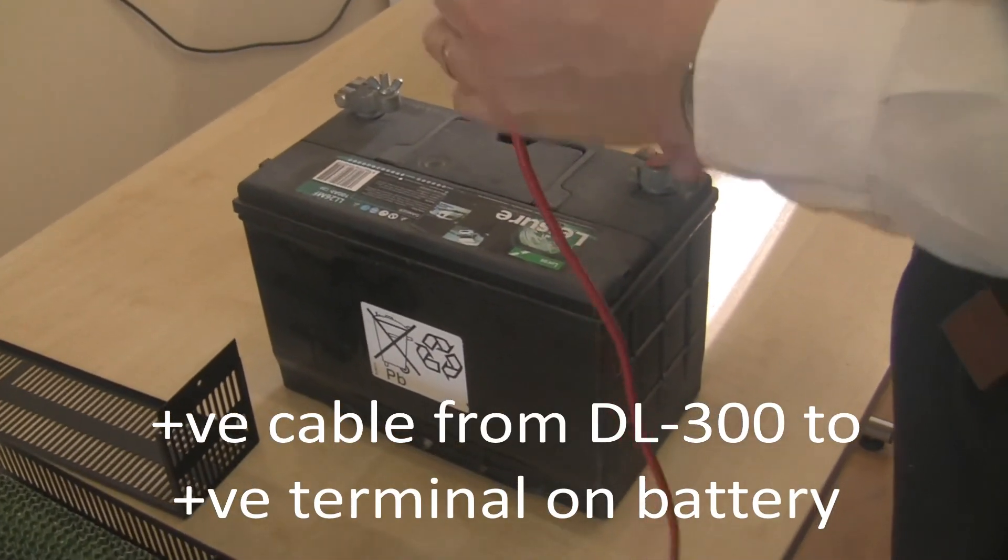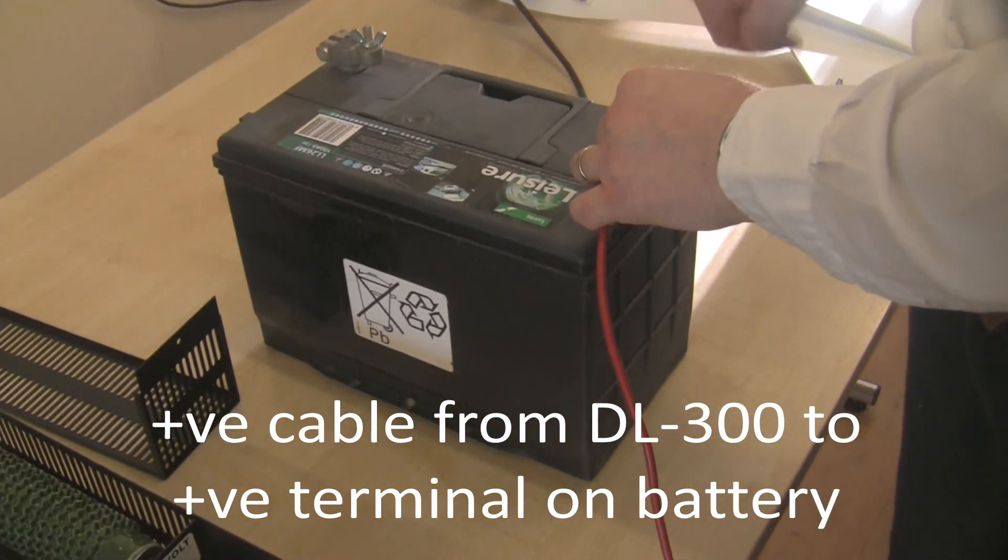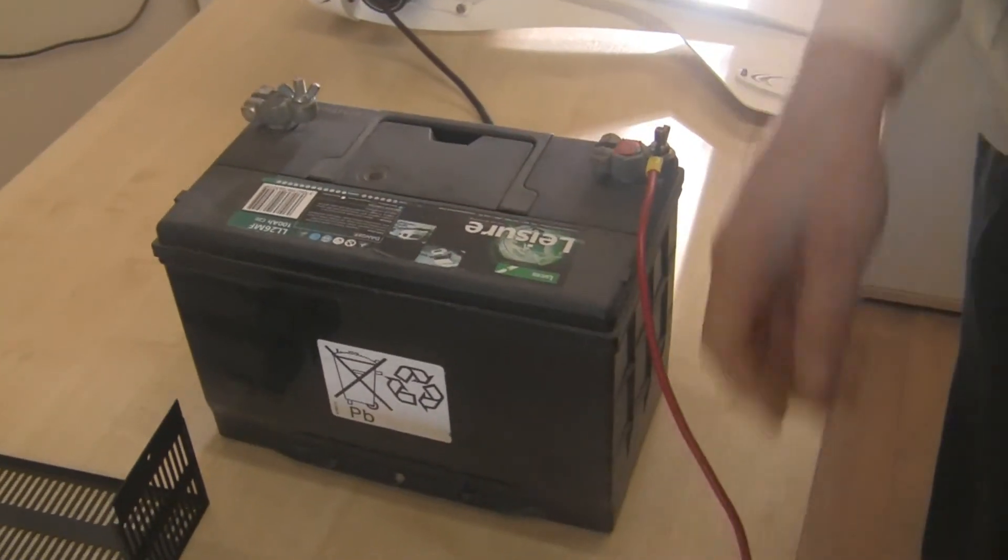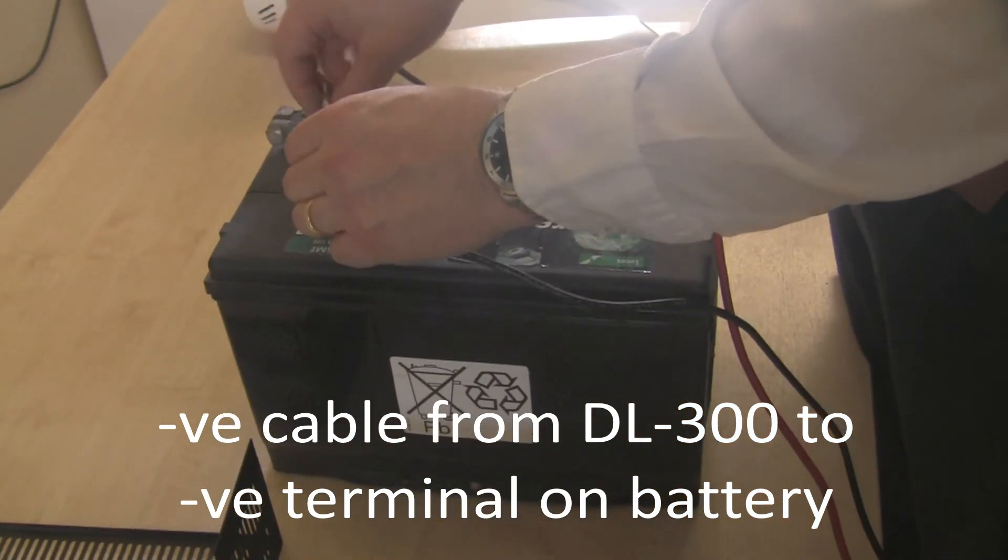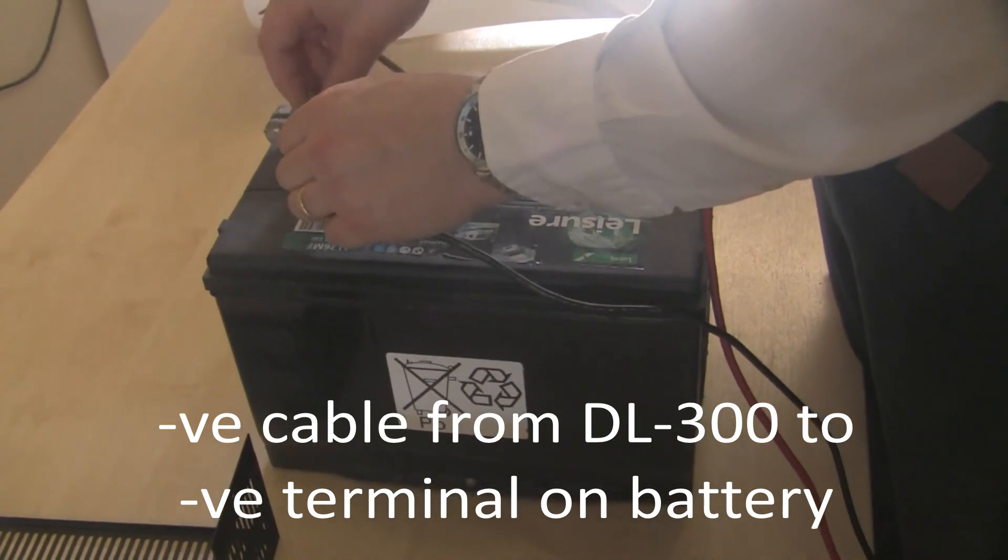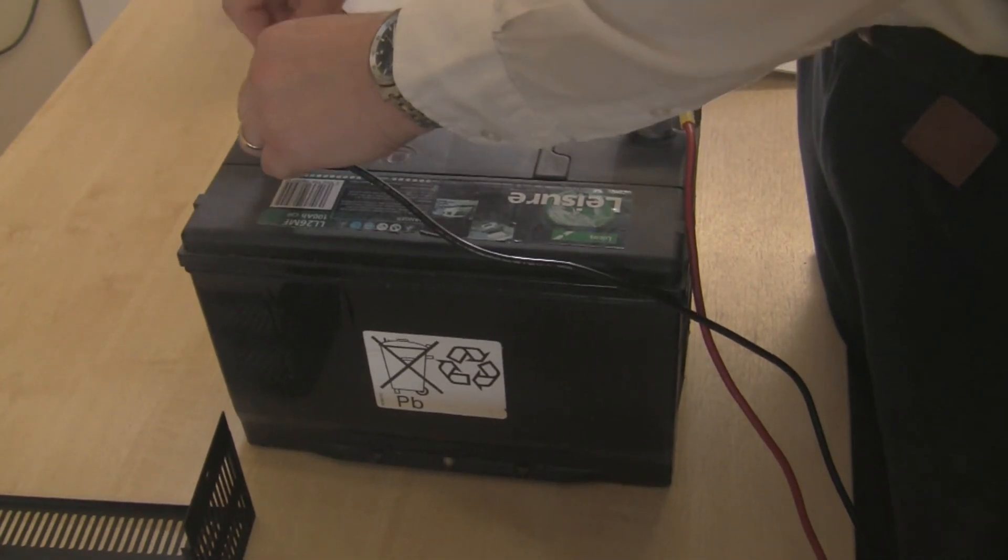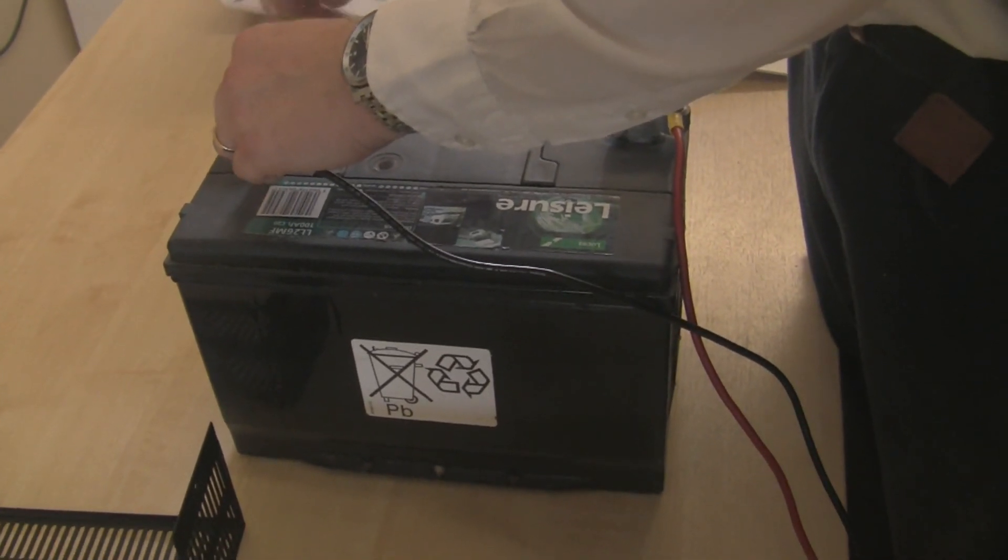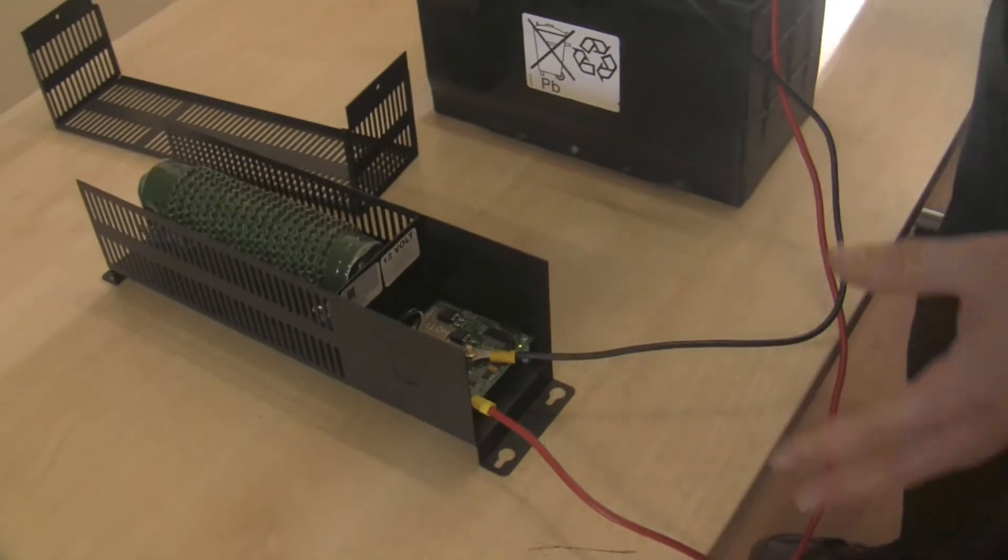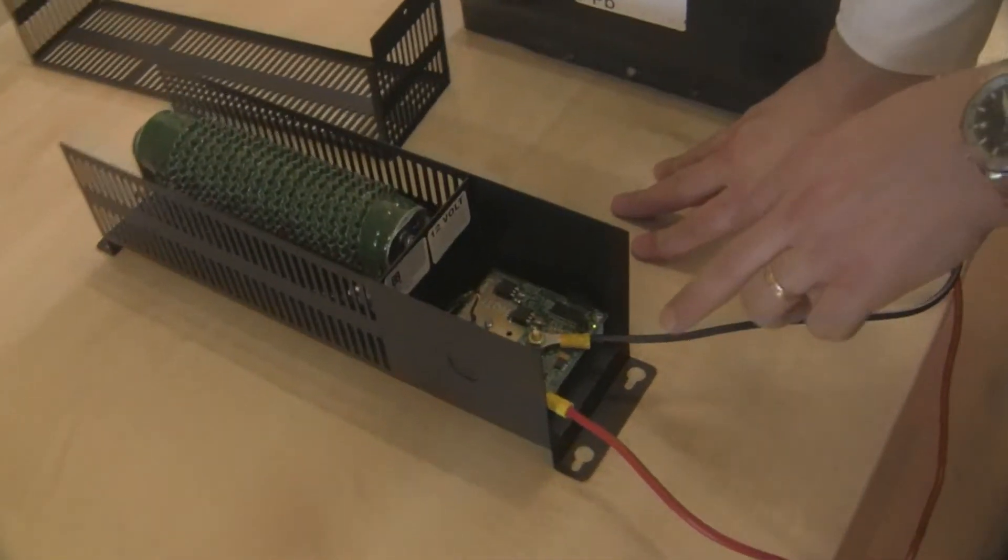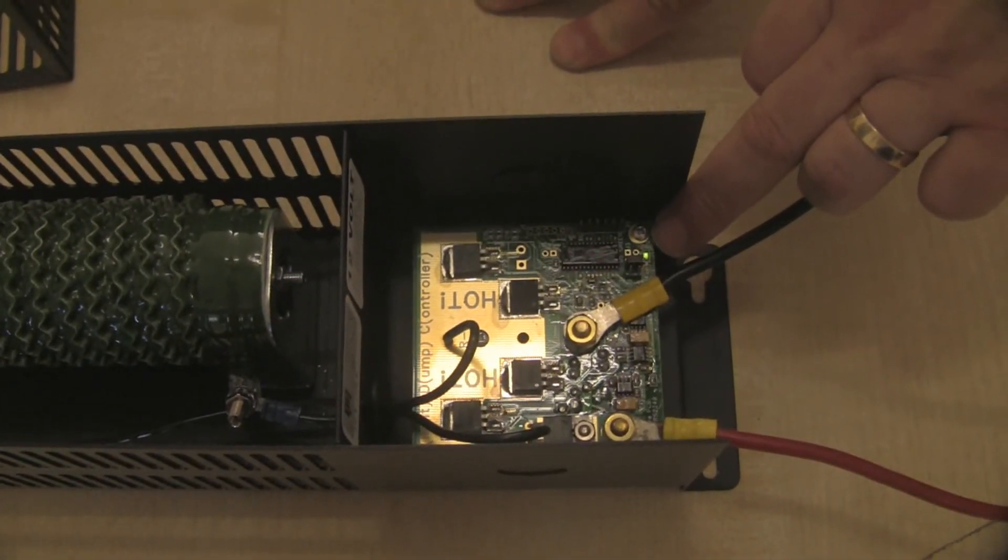So I'm connecting the positive cable from the positive terminal of the DL300 to the positive terminal of the battery, and I'm going to do the same thing with the negative terminal. When you're using batteries, obviously be very careful using tools around battery terminals. You don't want to short them out, otherwise there will be a big spark and the tool that's actually causing the short circuit will probably melt and possibly do you harm. So now I've connected that up, it's actually powered up the controller and you can possibly see there's a green LED, a very tiny green LED right at the tip of my finger, it's just lit up.